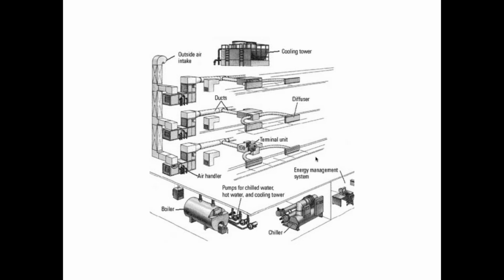It's a giveaway. If you see thermostats every couple of offices, you know it's a variable air volume system, that you have some sort of box that controls the air. If you only see one thermostat on the floor, it means that it's a constant volume system, only one thing controlling that the whole time.